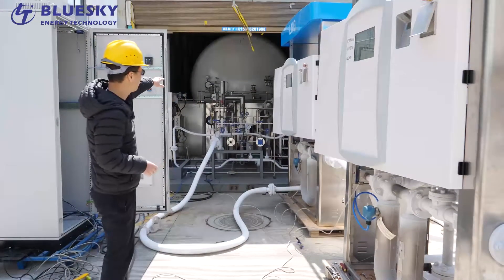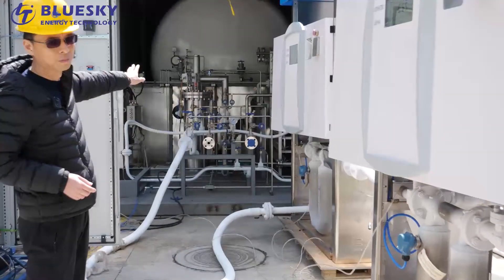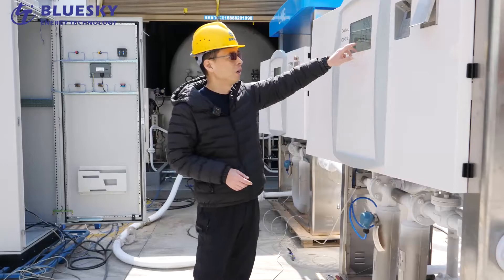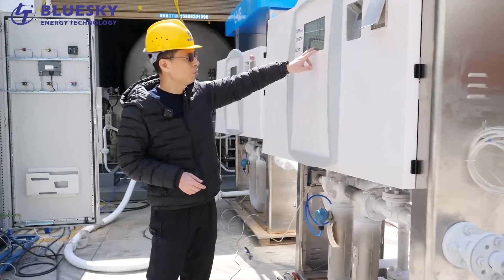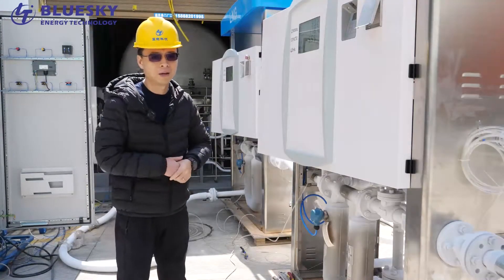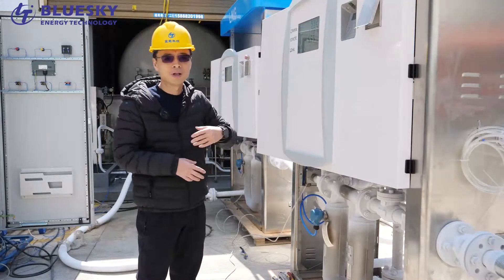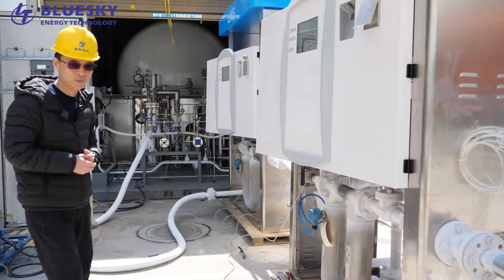Today the tank is full of liquid nitrogen and the internal temperature is around minus 170°C. When we start the test, liquid will come from the tank to the pump pool, which is already full of liquid. Before starting we need to pre-cool the whole machine. Before my speech started, after pre-cooling the temperature had reached minus 160°C, but after about five minutes of talking the temperature is already minus 100°C, so we need to redo the pre-cooling before dispenser testing.